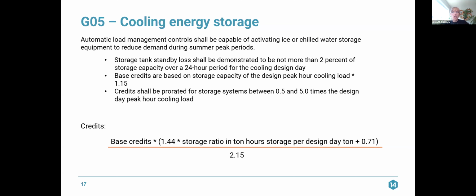The base credits in this section are calculated based on a storage capacity of the design peak hour cooling load times 1.15. So 15% excess capacity based on the design peak hour cooling load. And then credits are prorated. So if you're providing less than 15% excess capacity and you're down at 50% of your total peak cooling load capacity, you can still achieve credits, and you can only achieve credits up to 5 times the design day peak hour cooling load. The way those are calculated, you take the base credits available, multiply that by 1.44 times the storage ratio in ton hours of storage per design day ton, and add 0.71 and divide all that by 2.15.